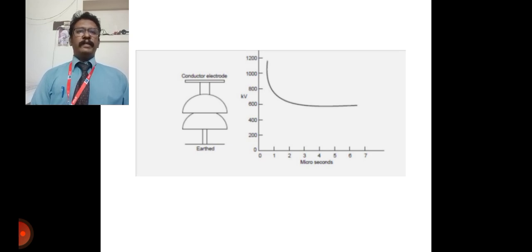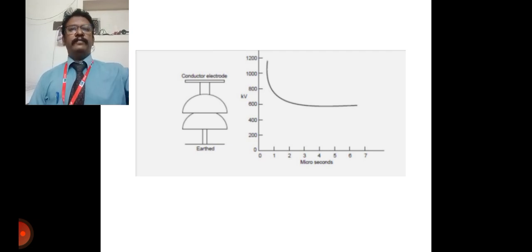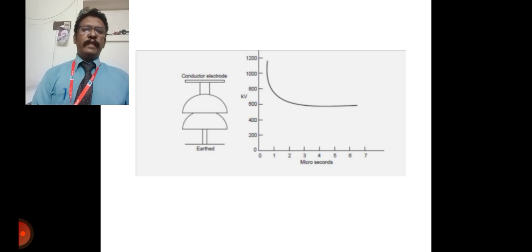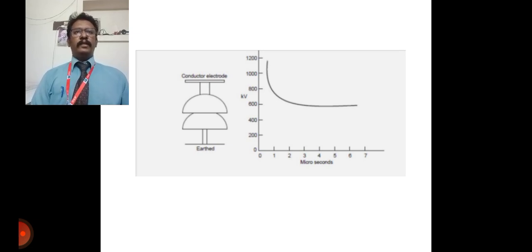This may take the form of arcing rings. Now the breakdown characteristics of a rod gap: for a given gap and wave shape of the voltage, the time for breakdown varies approximately inversely with the applied voltage. You can see the graph. Next, the time to flash over for a positive polarity is lower than that for the negative polarity, which normally happens in the arresters. Also, it is found that the flashover voltage depends to some extent on the length of the lower rod.